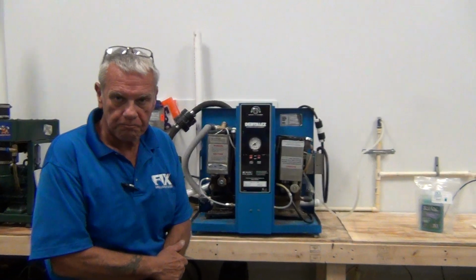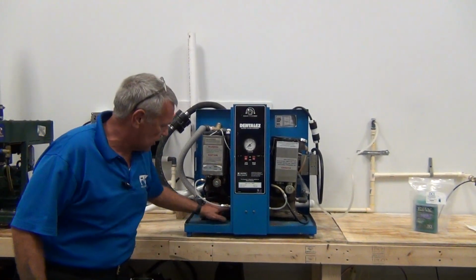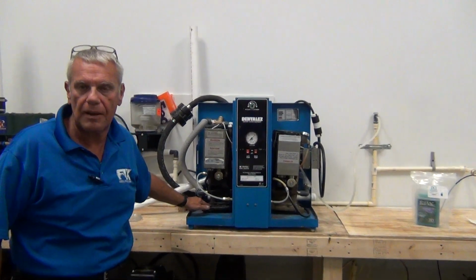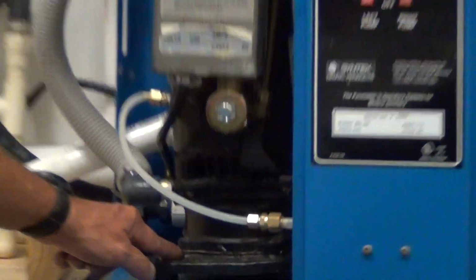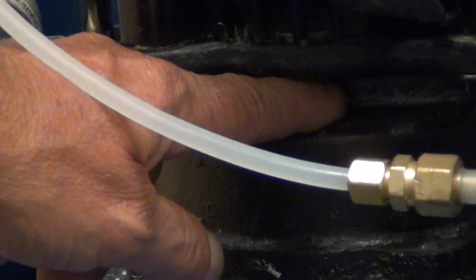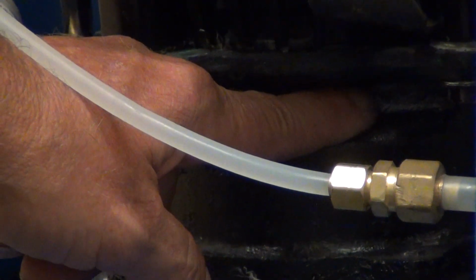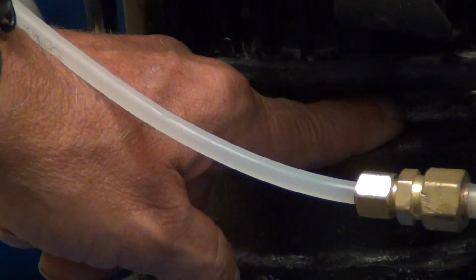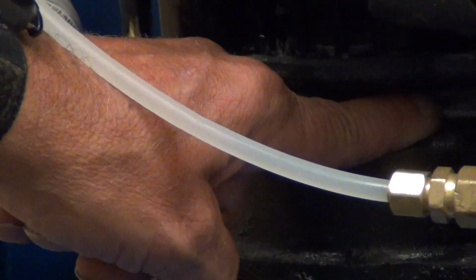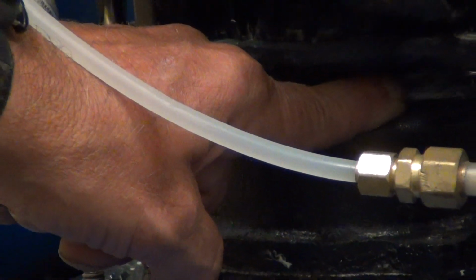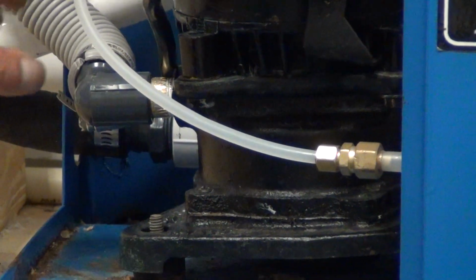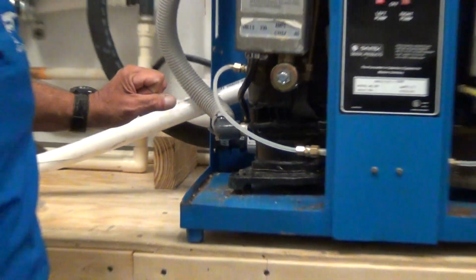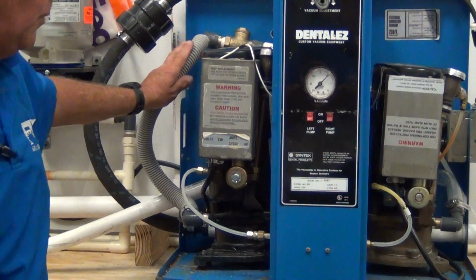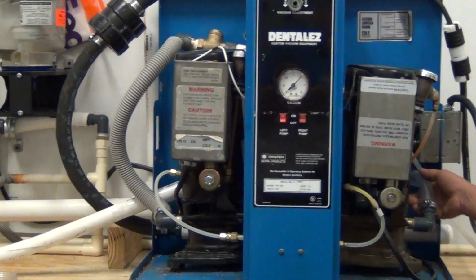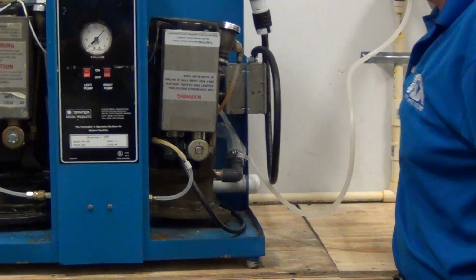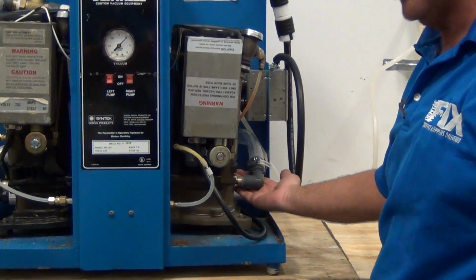Turn the pump back on, both motors. We're going to check around the platform, especially around the impeller gaskets, for signs of leakage. We have bleed holes, little actual openings into the impeller. If you see water coming out of the leak holes, that's an indication that the pump needs to be serviced. Probably an impeller seal. We also want to check all of our junctions, all of our plumbing junctions and units, especially our discharge tubing. Our discharge tubings are clear and we have no leaks.